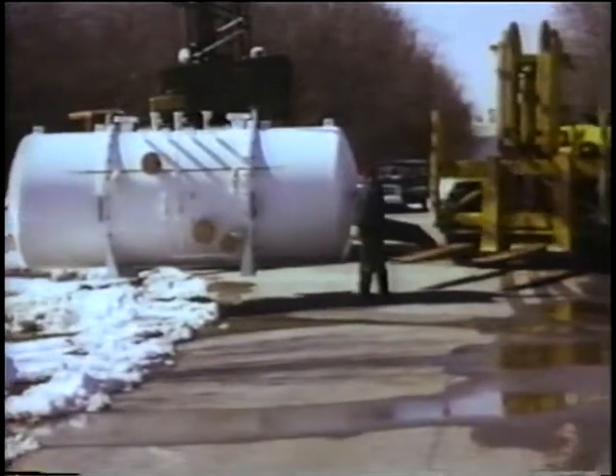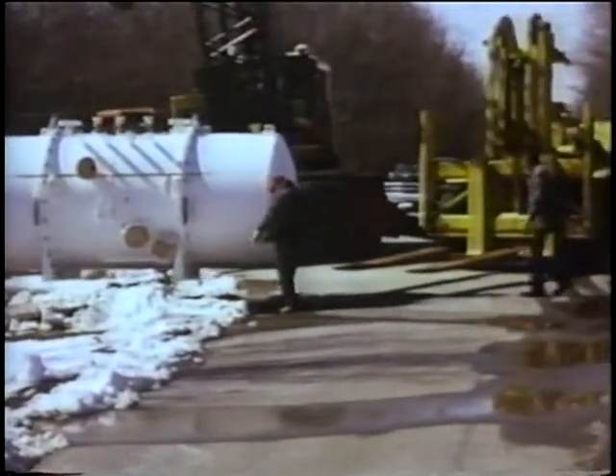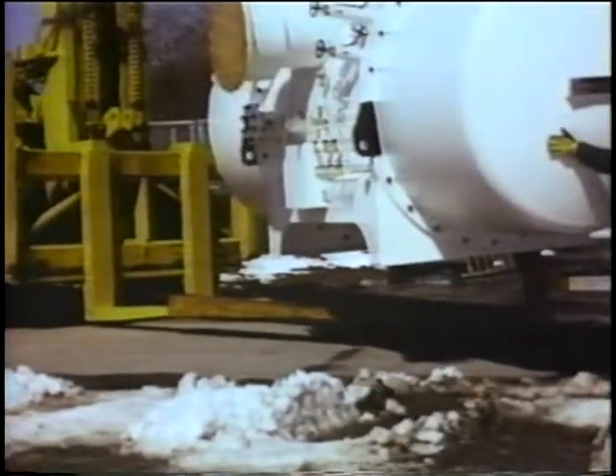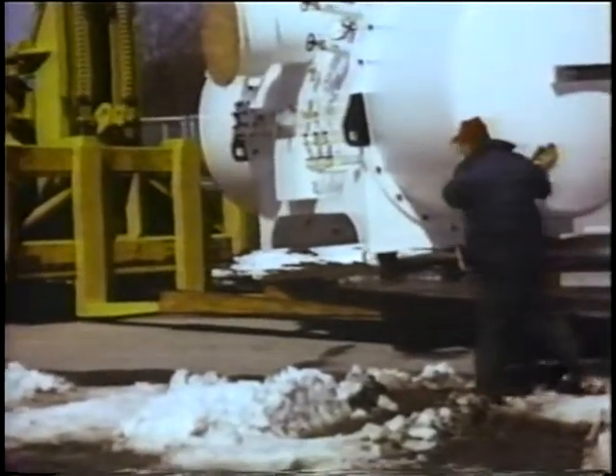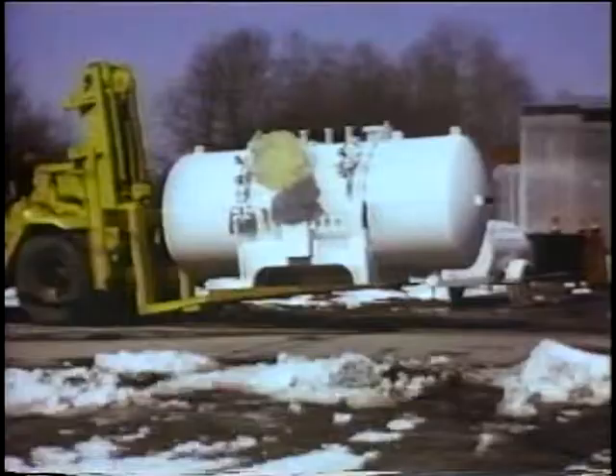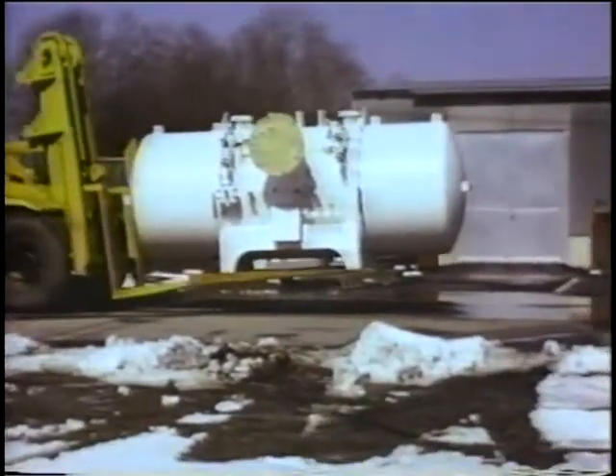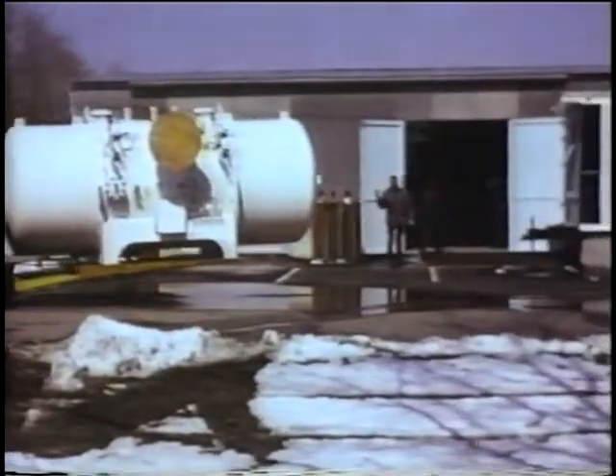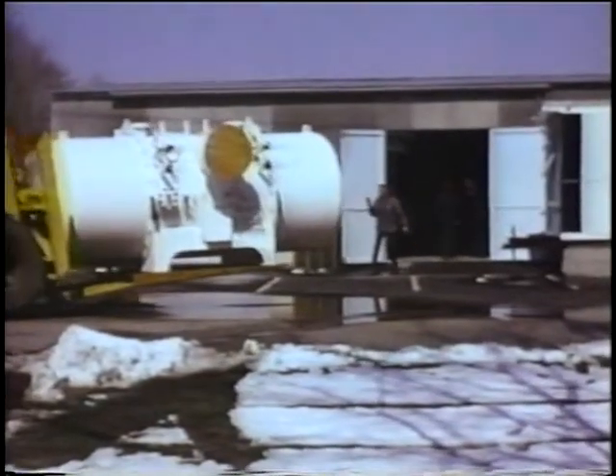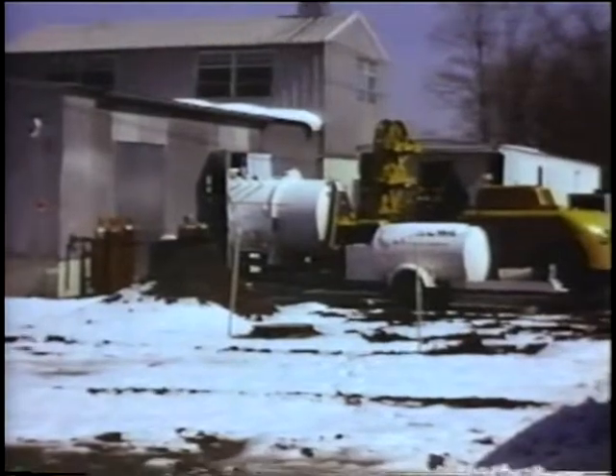The cables are cooled by a large helium refrigerator, seen here being rigged into the equipment room at the test facility. Helium is the only practical coolant for superconductors. In this installation, the refrigerator provides cold helium gas with a pressure of 225 pounds per square inch and at a temperature of about 7 degrees above absolute zero.